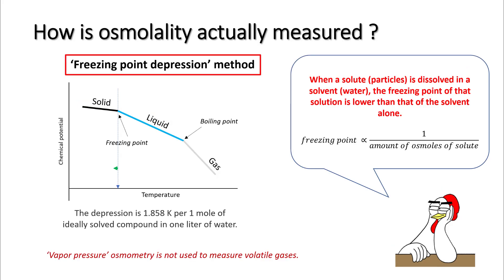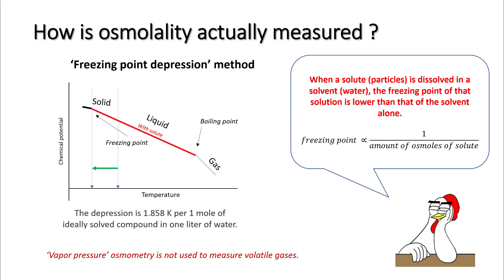Osmolality is measured by the freezing point depression method. When you dissolve a solute in water, the freezing point of water is lowered depending on the amount of osmols of solute present. By measuring the freezing point difference, you can calculate how many osmols are present.